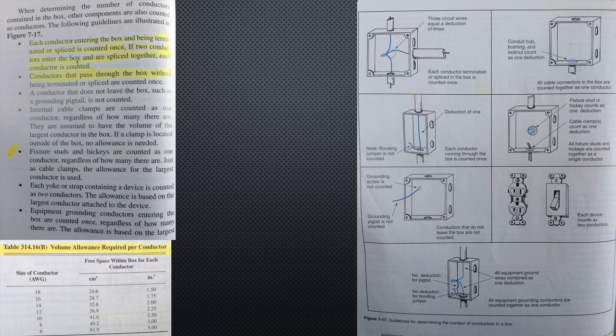Equipment grounding conductors entering the box are counted once, regardless of how many there are. The allowance is based on the largest conductor, or the largest equipment grounding conductor. If an additional set of equipment grounding conductors is present, a second allowance must be included.